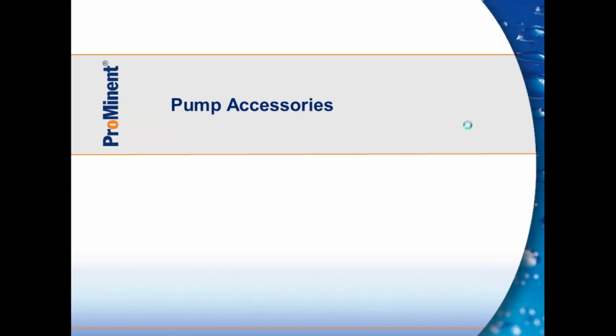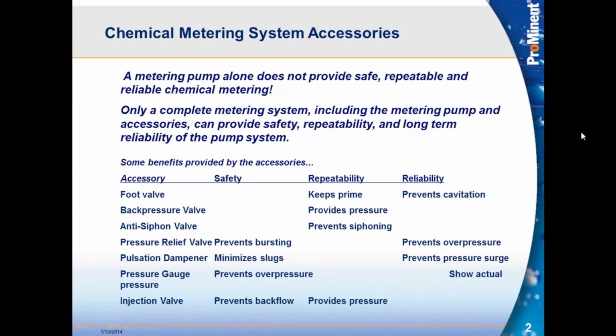With a metering pump, we want that pump to be repeatable. Each and every stroke of the pump should be the same volume for the customer. If the pump isn't seeing the back pressure regulated, then pressure and flow tend to be inverse, or flow can go through the pump. That check valve is going to prevent it from coming back through the pump in the opposite direction, but it will all day long allow flow to go in, we'll call it the forward direction. So it can siphon through. If we have a head pressure pushing through there and we don't have anything preventing it on the opposite end, it can push into the system or into the process unregulated. So we don't want that.